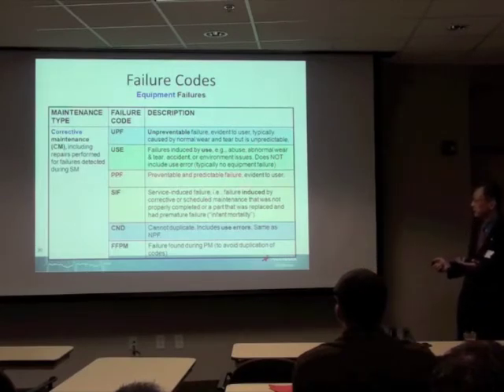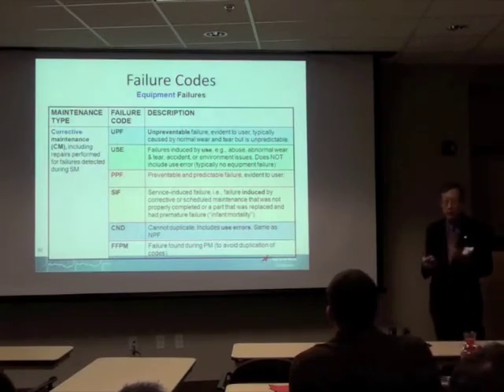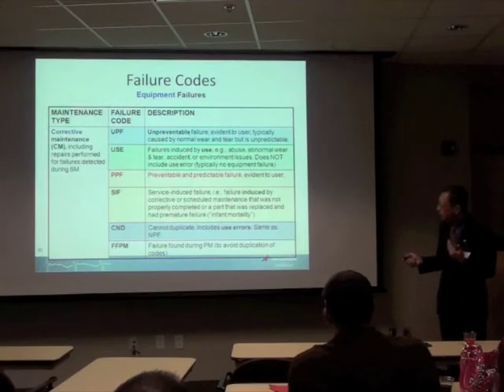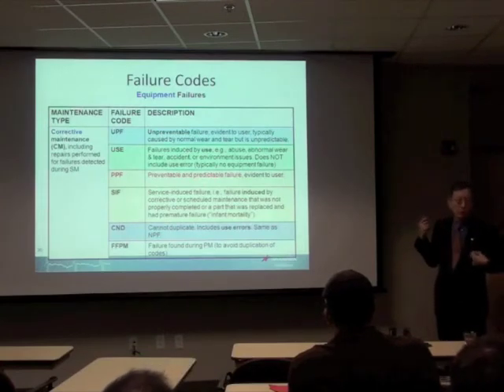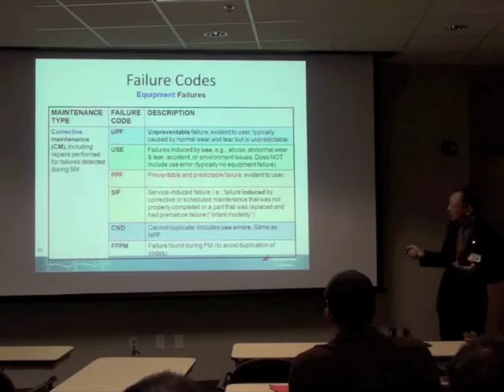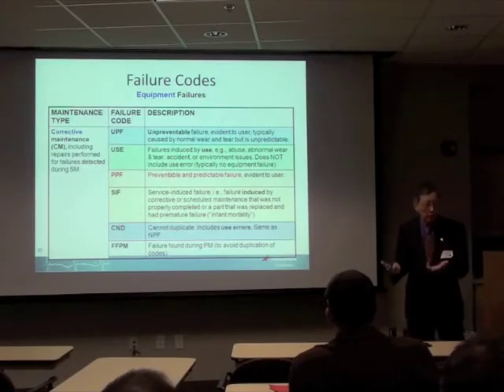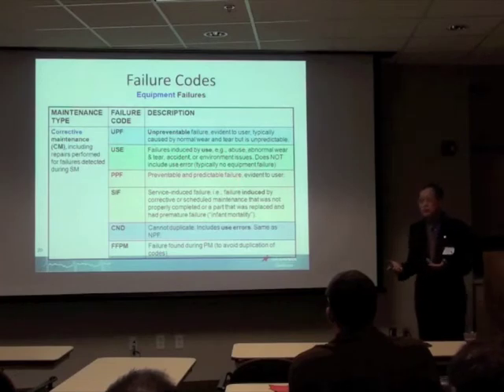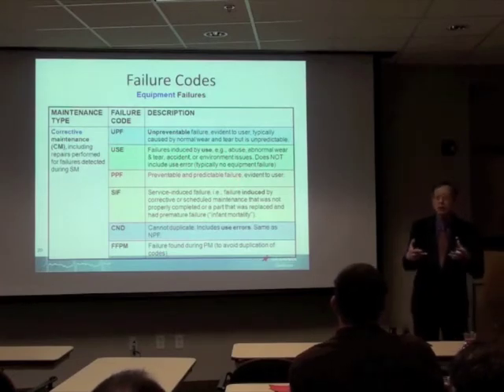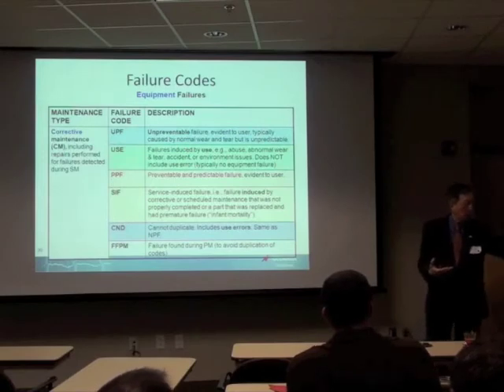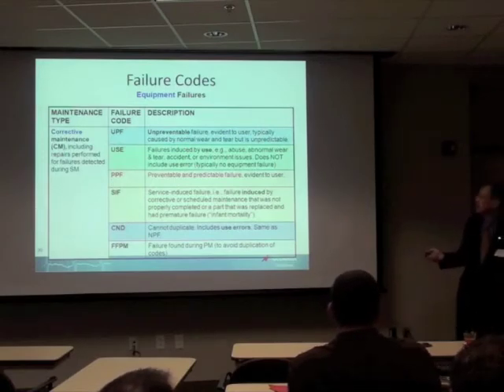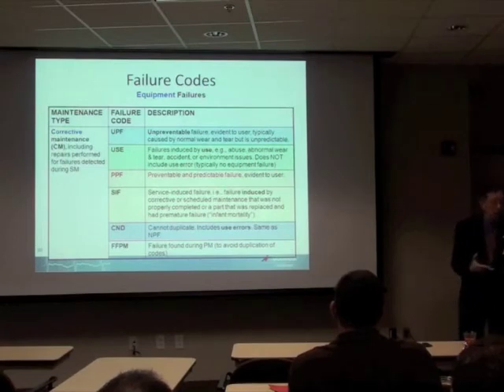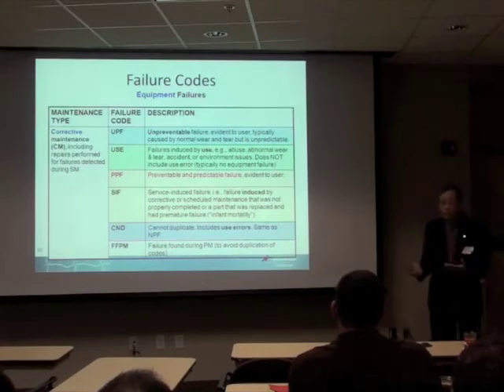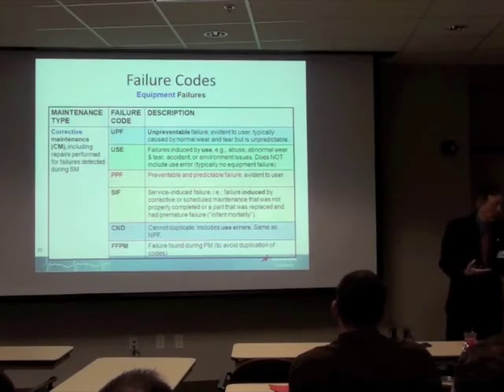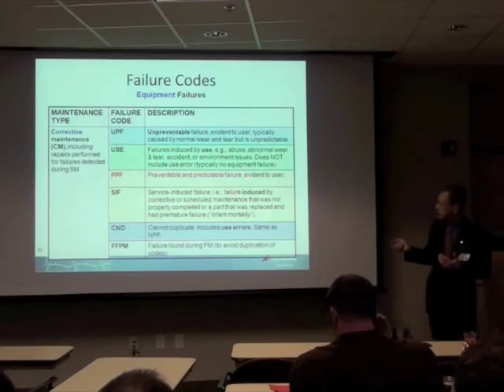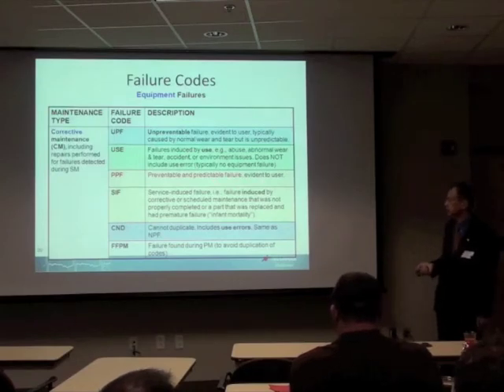Preventable and predictable failure - this is the kind of thing that we would like to catch. If we had caught it, then it would be on the scheduled maintenance side. But we did not catch it, so now it became a failure that we have to correct now. A good example is overheating of a device because dust has accumulated. You mentioned sand - this is something you guys have to consider. If you see a lot of repairs due to sand, you need to think about, hey, I need to do something to prevent it from happening if I can. Sometimes you may not, but this is a good example of something you need to think about.